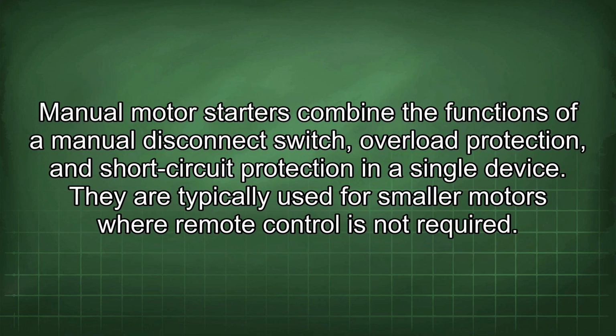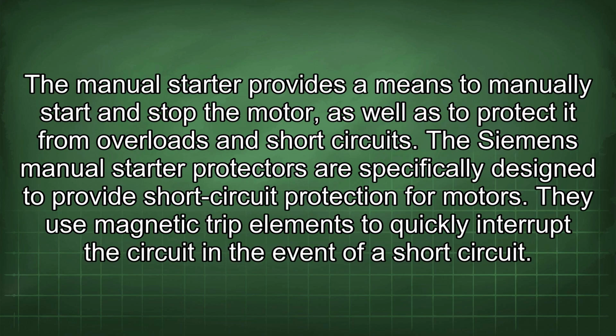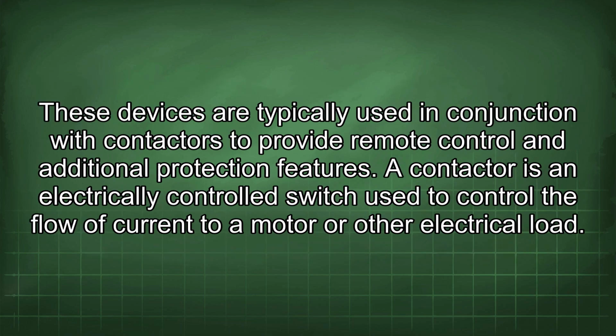Manual motor starters combine the functions of a manual disconnect switch, overload protection, and short circuit protection in a single device. They are typically used for smaller motors where remote control is not required. The manual starter provides a means to manually start and stop the motor, as well as to protect it from overloads and short circuits. The Siemens manual starter protectors are specifically designed to provide short circuit protection for motors. They use magnetic trip elements to quickly interrupt the circuit in the event of a short circuit. These devices are typically used in conjunction with contactors to provide remote control and additional protection features.